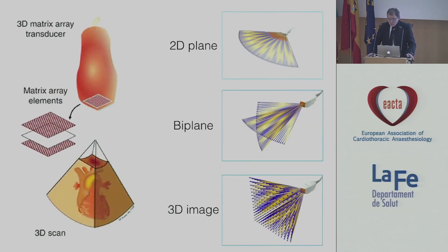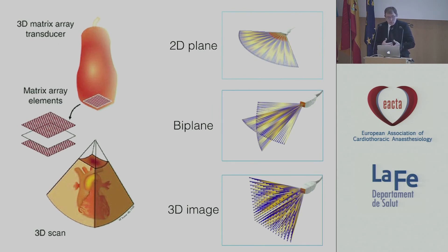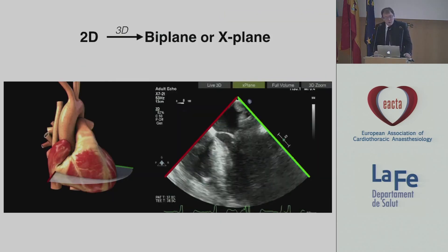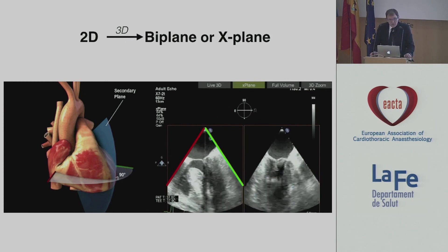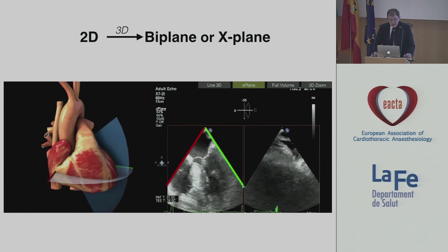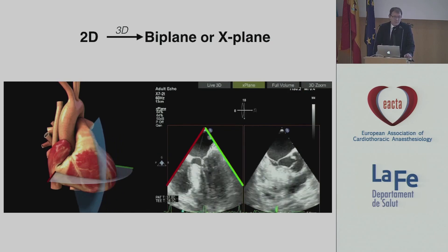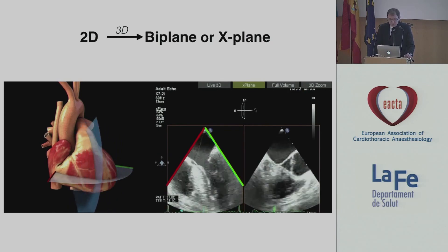Three-dimensional echocardiography uses matrix transducers which contain more than 3,000 elements. This allows us to get beautiful three-dimensional images, but we can also get two-dimensional planes — or even two two-dimensional planes at the same time, which is called biplane or x-plane. Your first image, for example the four-chamber view, can be used as a standard view, and the second view is perpendicular to this, allowing you to scan the whole heart, which is a very useful capability.